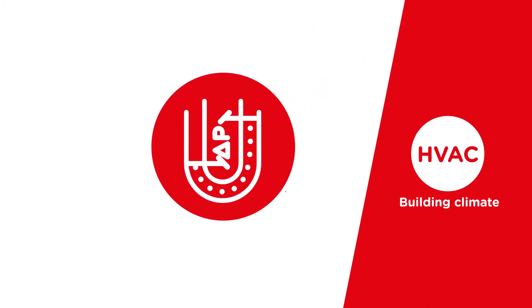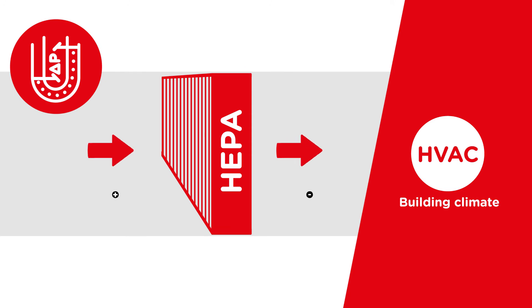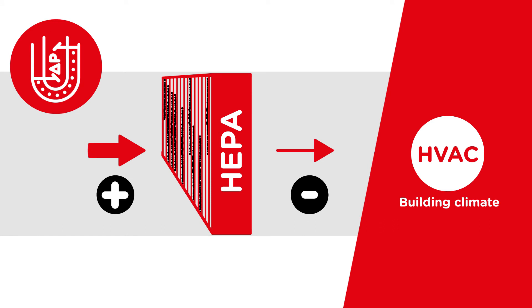Differential pressure is also important for maintaining balanced environmental conditions throughout a building. Dirty air filters increase resistance, leading to a fall in pressure. Monitoring the filter with a differential pressure sensor ensures optimal performance.